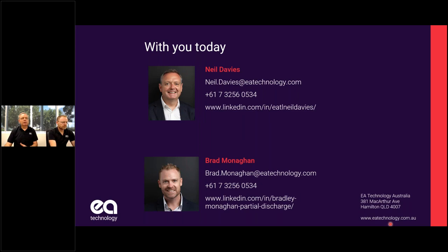So what you often find is that you can use very quick online testing to target where you want to use your expensive, time-consuming, outage-inducing, if you like, offline testing first. If you've got access to cable screens, we can probably test 30, 40 sets of cable terminations in a day without much problem, depending on whether you've got travel. If you are testing offline, it's one or two cables a day.